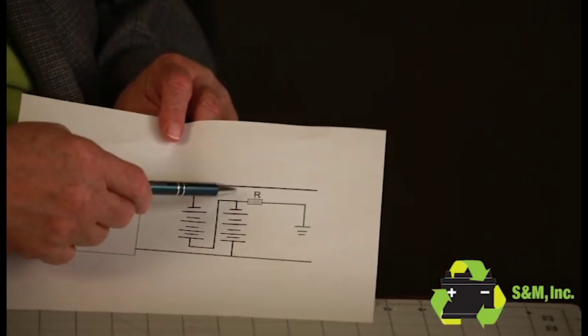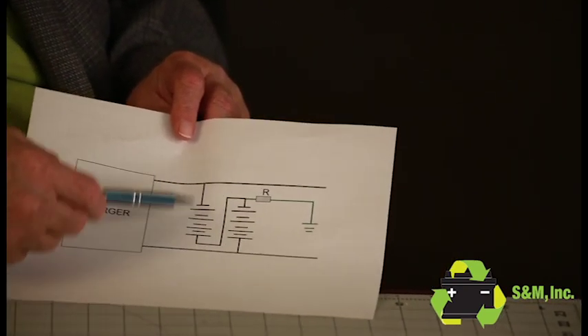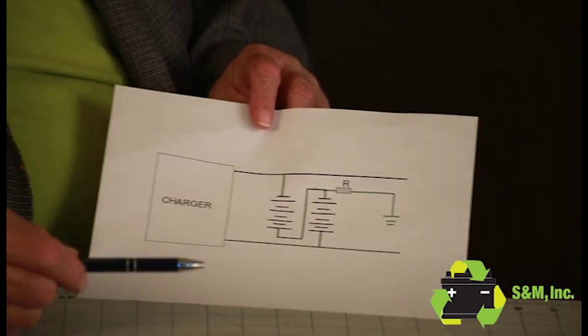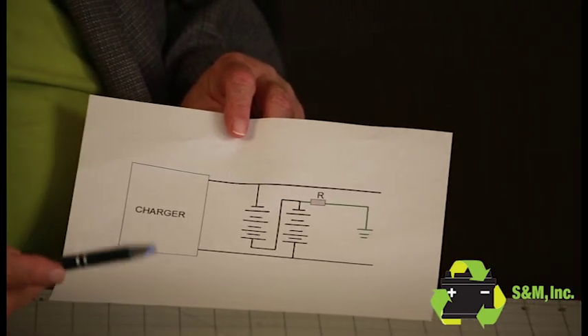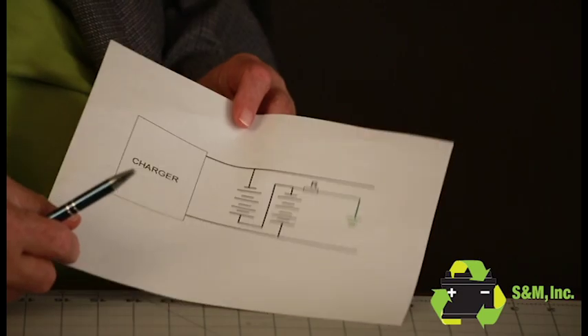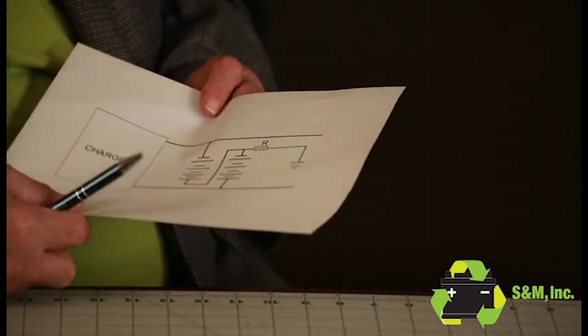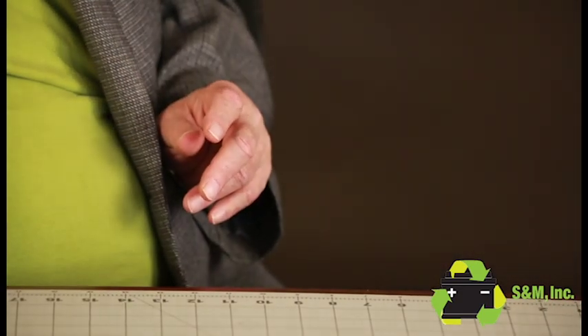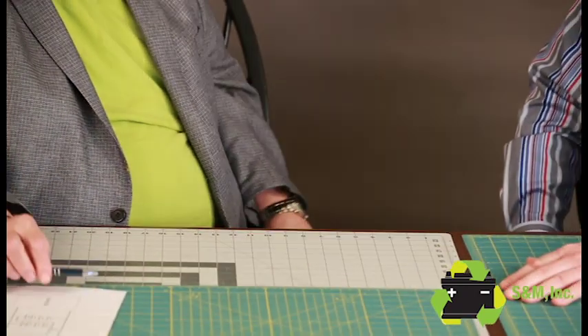It's a center tap battery here, and then they break it with disconnect switches to reduce the voltage for the technician. That's a big deal in battery maintenance right now. Some of the NFPA standards and whatnot are looking at how much voltage somebody could get across and get hurt, or whether there's an arc flash, arc blast condition.